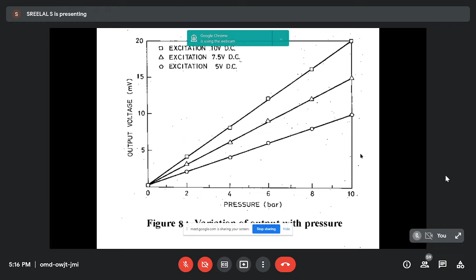So this is a MEMS pressure sensor which we have developed back in ISRO. It has a pressure range of 0 to 1 bar. It has a proof pressure of 2 bar, that is, the maximum pressure that you can apply without degrading the sensor characteristics. Then it has a burst pressure, that is a damaging pressure, of 4 bar.